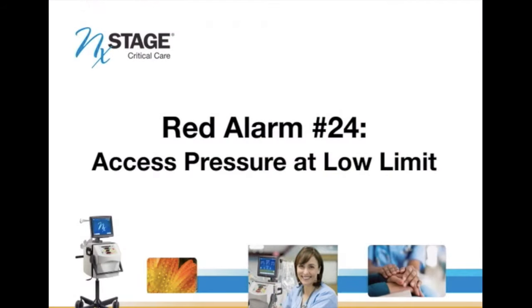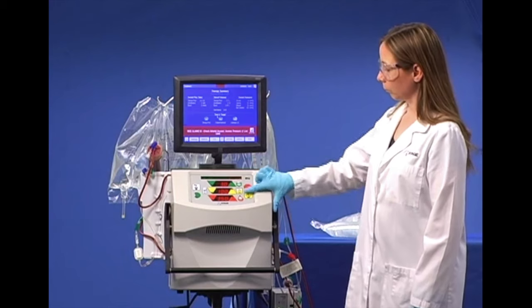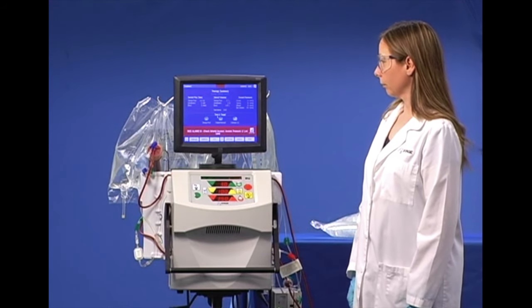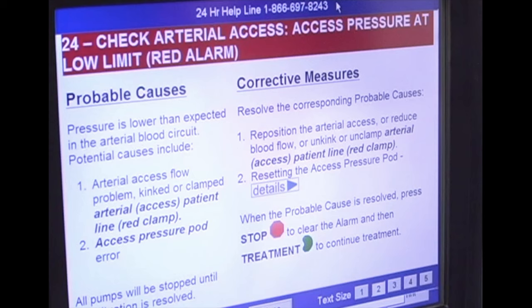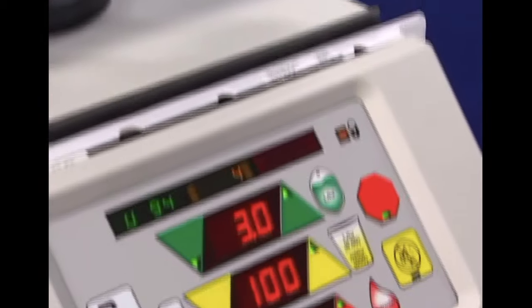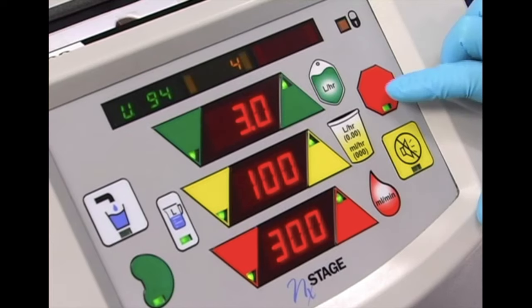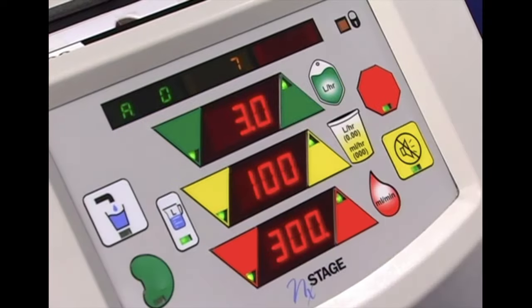Let's review red alarm number 24: access pressure at low limit. When the alarm sounds, note the condition bar for the type of alarm. Press Mute to silence the audible alarm. Click on More Info on the OneView status bar. This alarm is identifying a flow problem from the patient's vascular access. Follow your hospital's protocol for troubleshooting vascular access. Once the problem has been resolved, push the Stop key. Pressing the Stop key after an alarm lets the machine know you have corrected the problem and resets the alarm. Next, press the Treatment button to continue therapy and make sure your pumps are turned on.